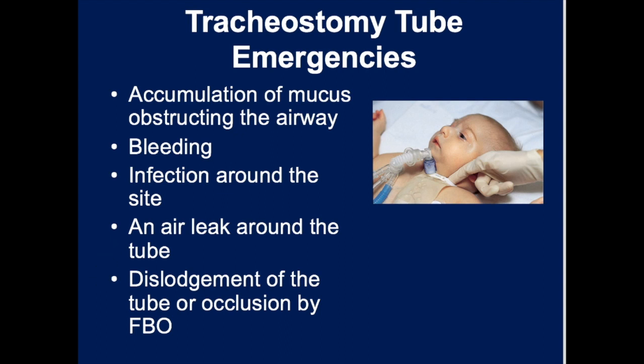What this is: some of these tubes are what's called cuffed, which means they have a balloon around the tube that inflates. It's kind of like an ET tube. You put the tracheostomy in and inflate the cuff, and it holds the tracheostomy in place and prevents air from flowing outside of it. If the patient is supposed to have that cuff on there and it's ruptured and doesn't hold air, then the air can move around the tracheostomy, and it's not directed where it's supposed to go. If a patient is trying to breathe in through the tracheostomy site, the balloon is supposed to prevent that air from going up and out the mouth. So if the patient's on a ventilator, for example, and you have pressure pushing the air in, if you have a cuff leak, the air isn't being directed down into the lungs where it's supposed to go. It can also escape through the nose and mouth, and that's called an air leak.